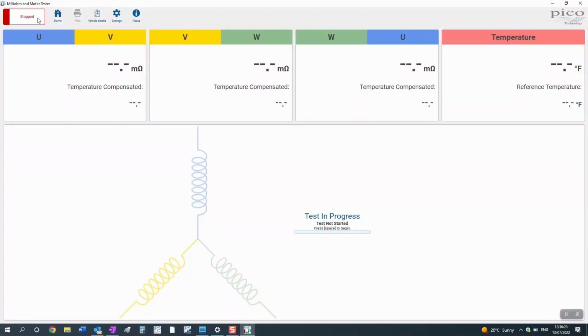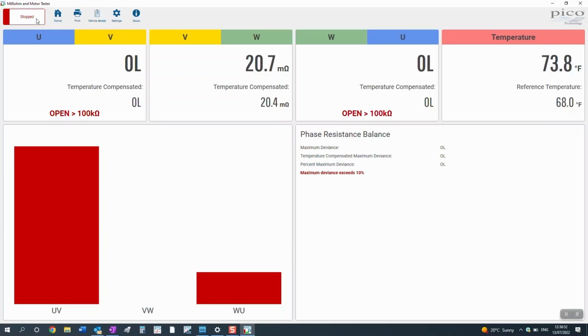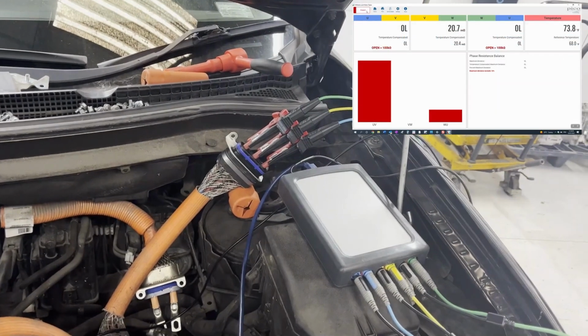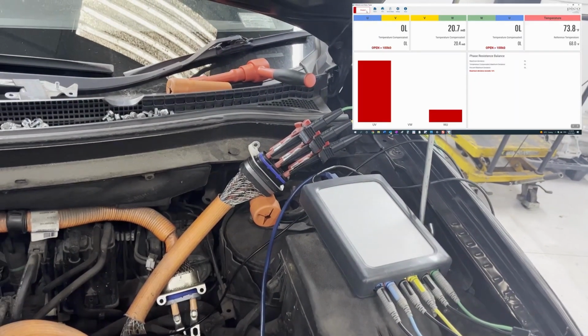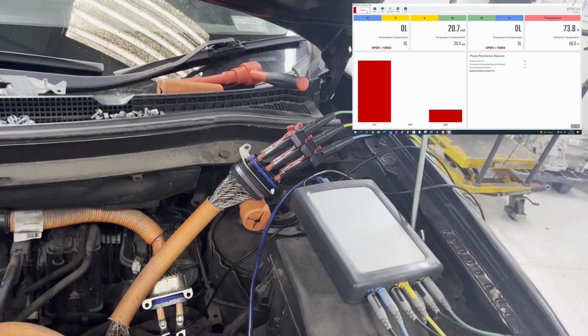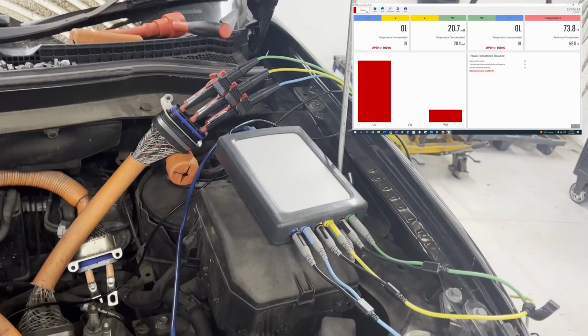All right, so here we go. We press the stop button. The software is now running, and you'll see in the software that we've actually got a temperature value top right-hand corner, 73.8 Fahrenheit. Notice how it's doing a resistance check through each coil. It's waiting for the voltage to stabilize, and it's then also reversing as well. So that's allowing for any dissimilar metal issues or connectivity issues. So we'll measure the resistance in one direction and then the other, then find the average. I can't stress enough just how important it is to have good connections when it comes to this check. Resistance, milliohm resistance increases dramatically with poor connection. So if you've got a poor connection at your cable, we're going to have an error in the measurement.